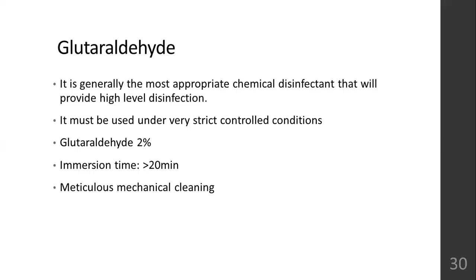Glutaraldehyde is generally the most appropriate disinfectant that can give you high-level disinfection, and it must be used under very strictly controlled conditions. Glutaraldehyde 2% is the most potent form of disinfectant, and you just require 20 minutes of immersion time to achieve high-level disinfection. Meticulous mechanical cleaning is required before you immerse any equipment or instrument in glutaraldehyde solution. Instruments that are dirty, soiled, and have organic material stuck to them are not ideal for glutaraldehyde solution. Manual cleaning has to be done properly before immersing any instrument in glutaraldehyde 2% solution.